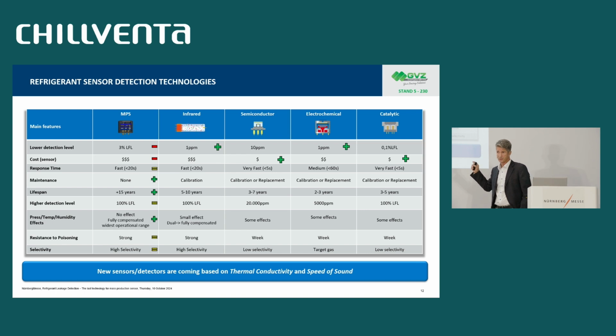Quickly, you see MPS is not the best solution for cost reasons and also for the lower detection limit. It's not a technology good to be used for ppm or ppb concentration. It starts reading from a range of, let's say, 3% LFL or 400 ppm.